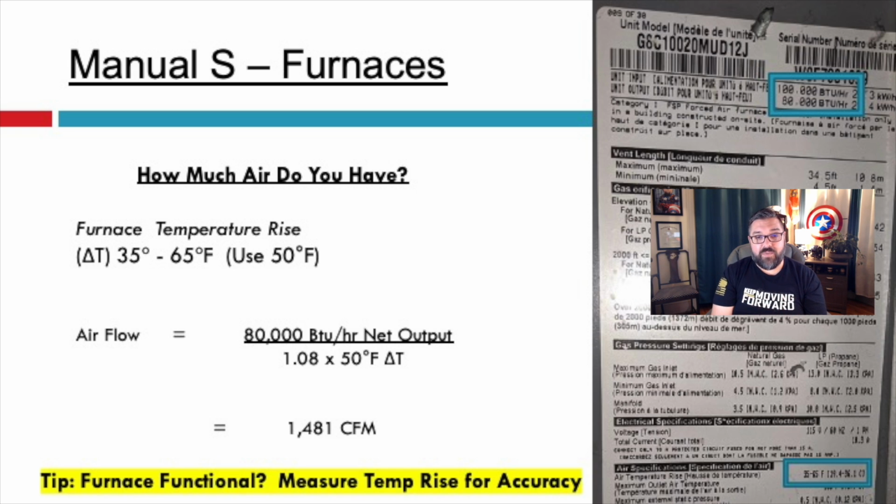Now, I highly recommend you either measure CFM this way by measuring delta T by running the furnace, or you use something like a TrueFlow plate or total external static pressure and using a blower chart if you can to get the actual CFM, all right? Then we're going to actually select the replacement furnace.